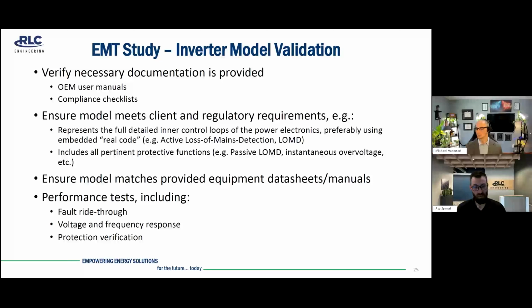So the first one represents the full detailed control loops of the power electronics, preferably using embedded real code. And what real code means is the code used in the inverter firmware and the actual field installation is represented in the PSCAD model. This is hopefully always the case, but in some cases it's not, and that's what these checklists are aiming to ensure, that they're a close enough match with reality.